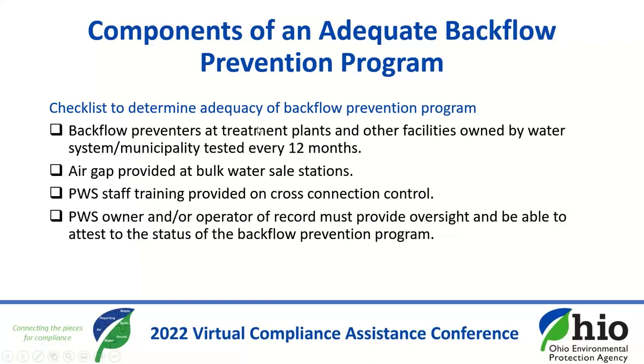You need to ensure that backflow prevention needs for all water connections have been identified and addressed through initial inspections, periodic surveys, and investigations every five years to determine current water use practices. You need a mechanism to identify needs on new connections as well as existing connections. Don't forget about backflow preventers located within your treatment plants and other facilities owned by the public water system — these also must be tested every 12 months. We want air gaps provided at bulk water sales stations. We highly encourage public water system staff to receive training on cross-connection control and backflow prevention. The public water system owner or operator of record must be able to provide oversight and attest to the status of the backflow prevention program.